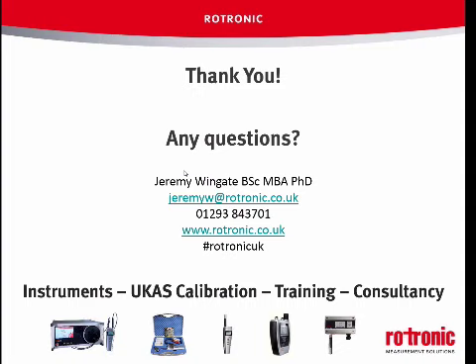Just before I go on to some system questions, I just had a question here. The question was on the good old true wet bulb thermometer. The requirement is to use distilled water with those. Does it matter if people don't use distilled water? It will affect the fundamental physics of it: the depression that you expect is based on pure water, distilled water, very, very pure water, and a very clean wick.